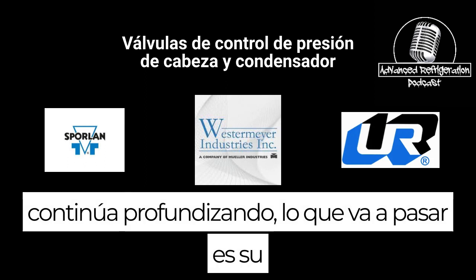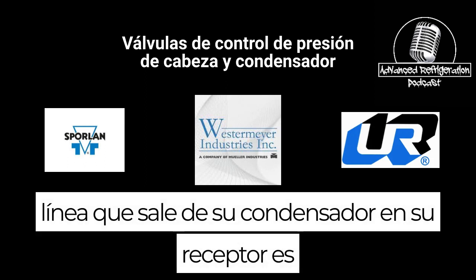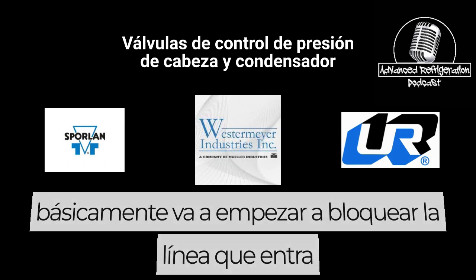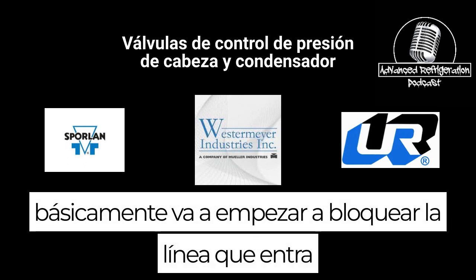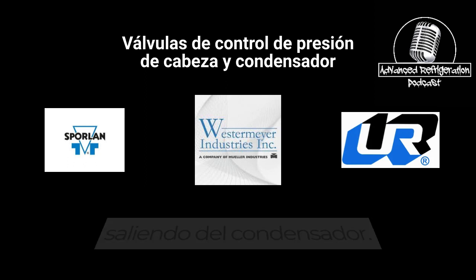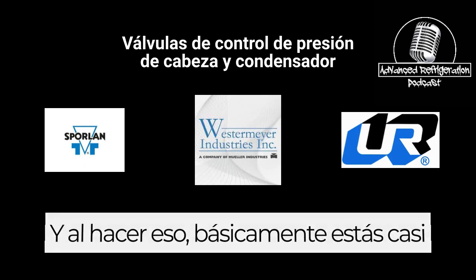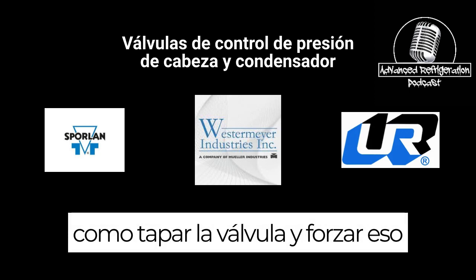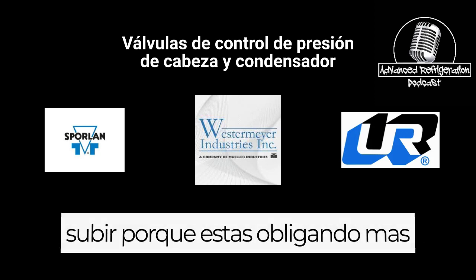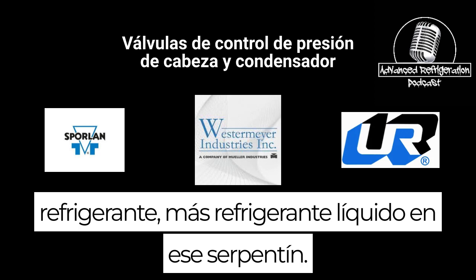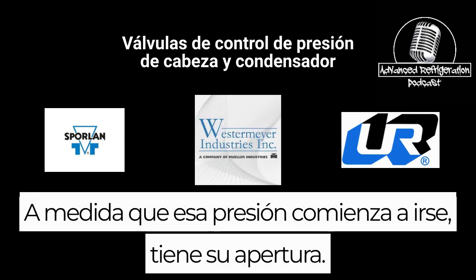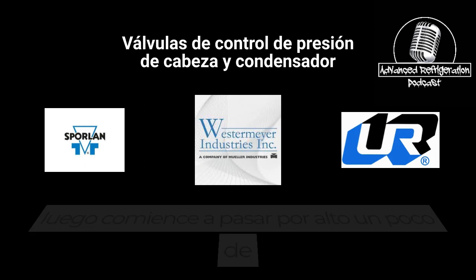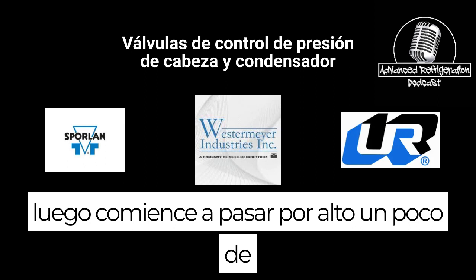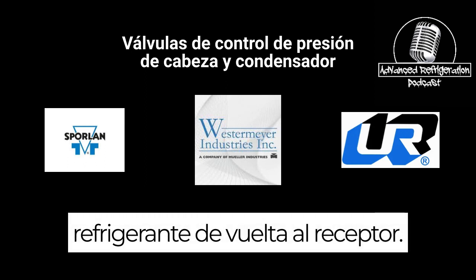What's going to happen is the line coming out of your condenser into your receiver is going to start blocking off. By doing that, you're almost like shutting the valve and forcing the pressure to go up, because you're forcing more liquid refrigerant into that coil. As that pressure starts to go up, as it's opening, the discharge line is going to start bypassing a little bit of refrigerant back into the receiver.